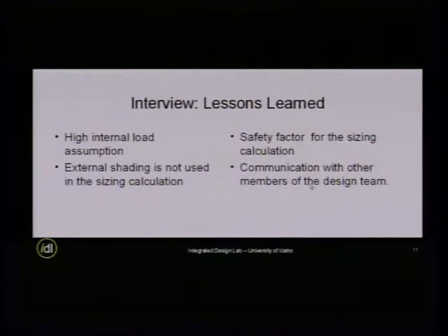And then the communication with other members of the team can lead to oversizing. For example, the initial design drawing came with a window type that is not so good. So the mechanical engineering team calculated the sizing with the not so good window. Then the architects and the owner worked out the cost plan, and at the last minute they came out with a better window. But the feedback to the mechanical engineering team is too late, and sometimes they don't have time to redo the calculation. So the building ends up built with better glass, with air conditioning that is calculated with the worse glass. So oversized, for sure.